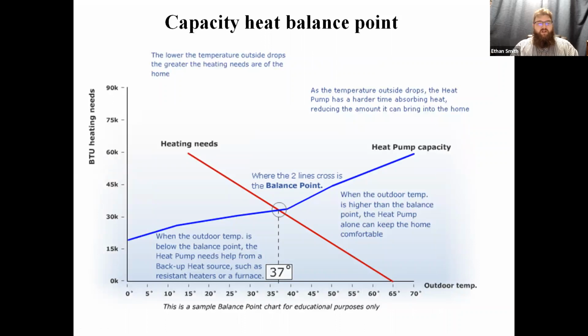So we've got two lines here. We've got our heating need line in red and our heat pump capacity in blue. You'll notice as the temperature outside on the bottom here goes down, our heating needs go up, and our heat pump capacity goes down as well. So where those two lines cross at that outdoor temperature, my system is in perfect balance. I'm providing just enough heat for the house demand for that outdoor temperature. Okay, so I'm in perfect balance. Anytime I'm above that outdoor temperature, my heat pump is a little oversized. Anytime I'm below that temperature, my heat pump is not going to meet my heating need.